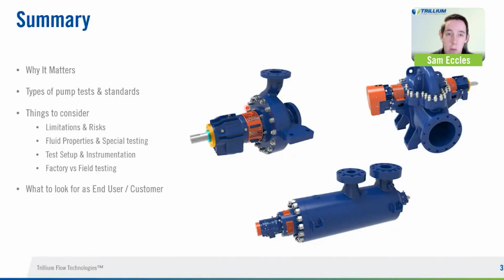Given a quick overview of the different types of pump tests and standards, we've talked about the risks predominantly around different fluid types, the fact that you're not on the same foundation, you're not doing what we would call a full string test or a full complete unit test. Talked about some of the impact on light hydrocarbons, how that affects NPSH, how it can also affect the risks of running back towards closed valve or zero flow. And we've talked about the test setup limitations and factory and field testing. And we finally just had a very quick run through from an end user.